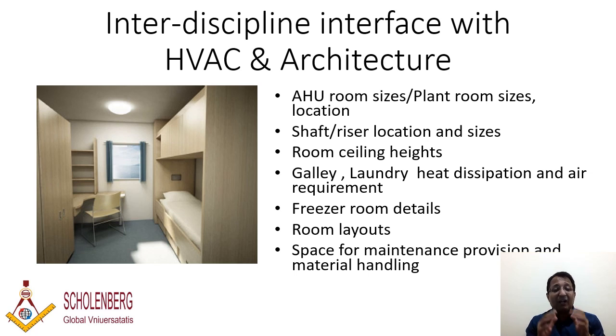Same for architecture - you need to ask for HVAC rooms, plant room size, location where you should keep your units, shaft or riser locations, and give them the respective sizes. Not only give it, you need to justify those sizes for the rooms and risers by making tentative drawings. Then ceiling and false ceiling heights, galley, laundry, heat dissipation, air conditioning requirement - all this you need to deal with the architectural discipline. Freezer room details also, because all freezer rooms come into the scope of the architect - he has to design the freezer rooms. Of course we design the cooling load, but he has to lay it out - it's his scope.